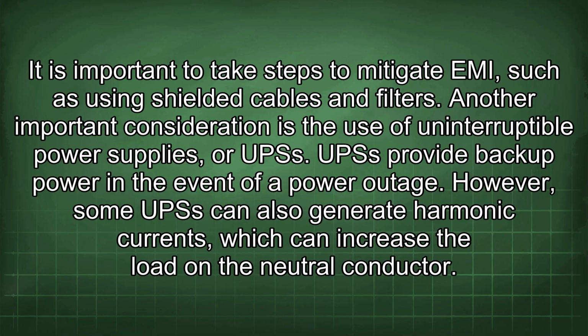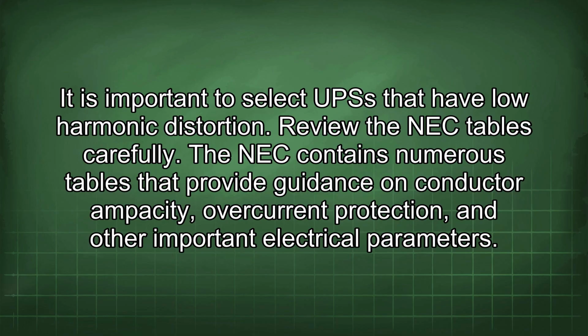Another important consideration is the use of uninterruptible power supplies, or UPSs. UPSs provide backup power in the event of a power outage. However, some UPSs can also generate harmonic currents, which can increase the load on the neutral conductor. It is important to select UPSs that have low harmonic distortion.